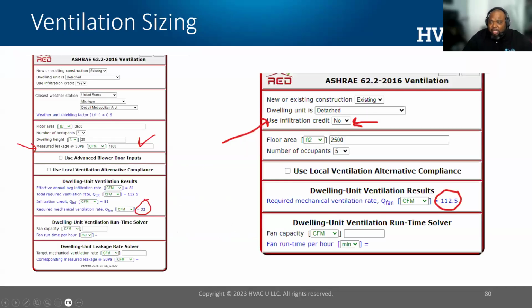And then going forward, looking at the left hand side of the screen, I will put the house square footage floor area inside. I will look at the number of occupants, which I will determine as the number of bedrooms plus one. And then I will put in the height of the dwelling. And if I were going to use the infiltration credit, I will put in my blower door number, that's my CFM50 number. And what this tool does is shake out exactly what the total ventilation rate is and then what fan you'll need to supply adequate ventilation. All right.